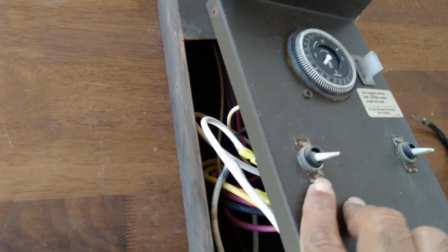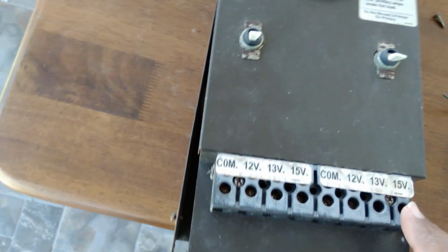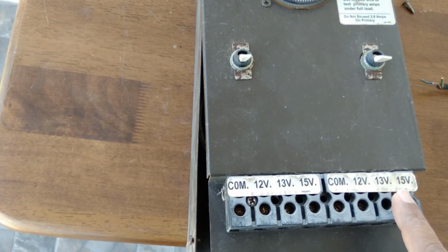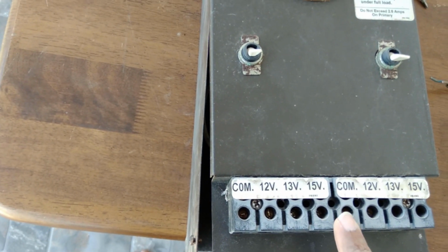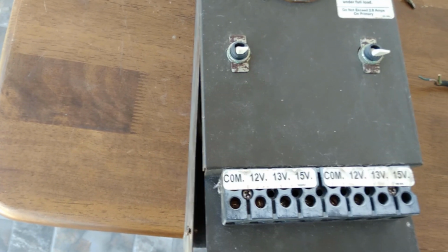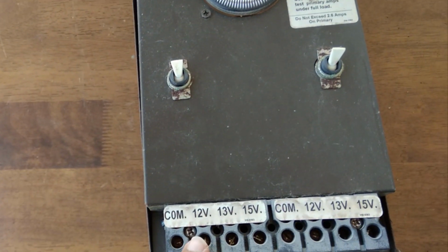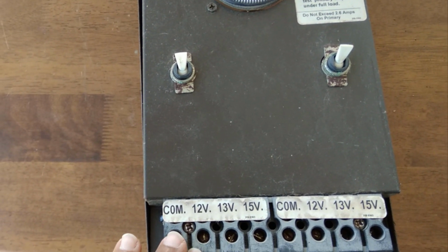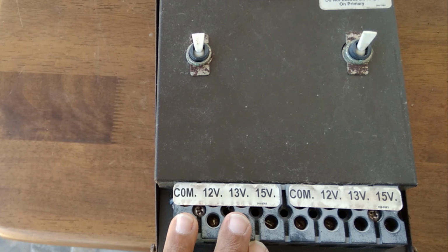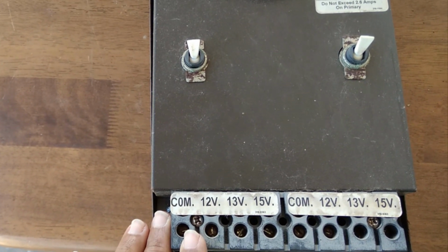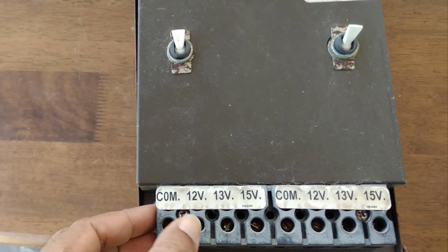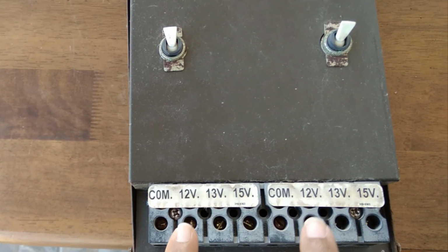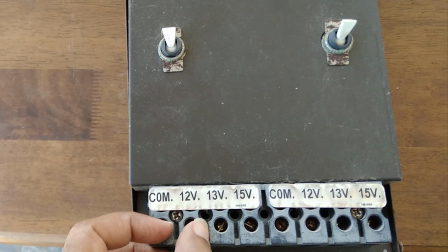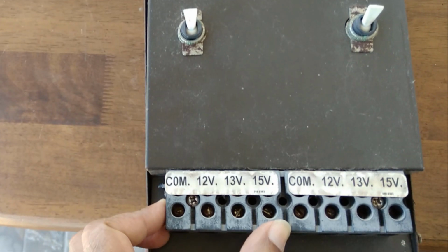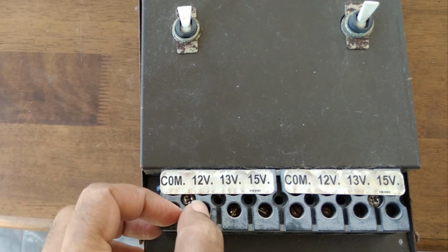So relatively simple. The one last thing to investigate: are these two connected? I think they're probably not. I would suspect it's two independent coils, but let's test that. After testing, it turns out these are actually connected. So maybe there's two independent coils, maybe there's one coil and it's split into two feed outs, but these are all connected. So you could get the 600 watts from just one set of terminals if you wanted to. In fact, probably just off the common and 12 if you needed to do that.